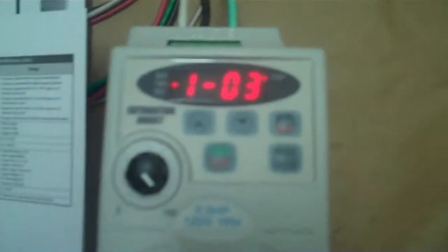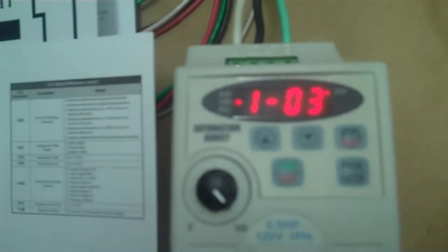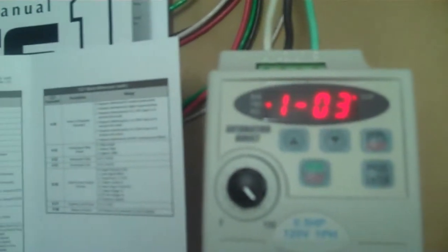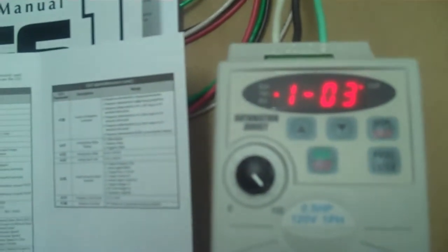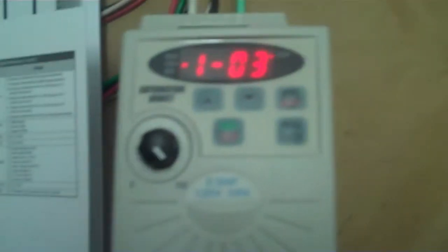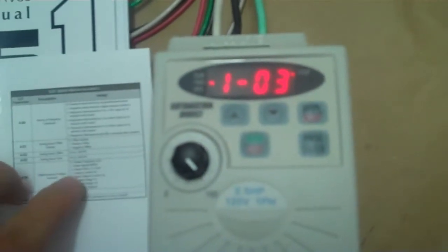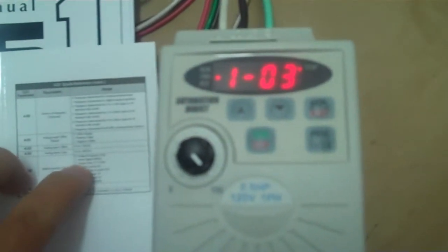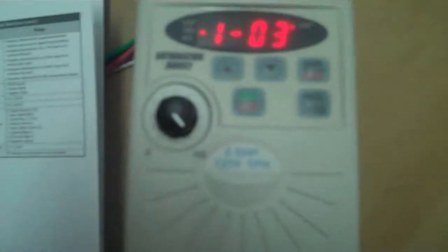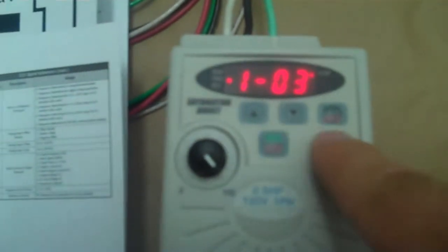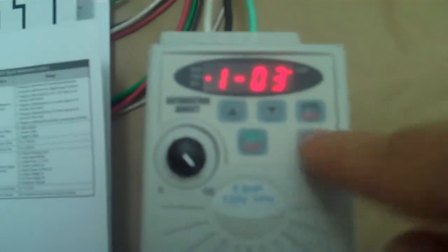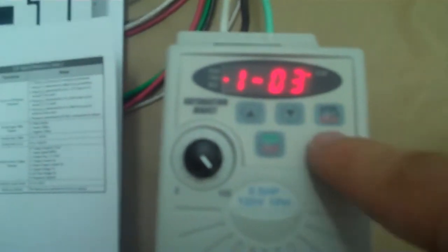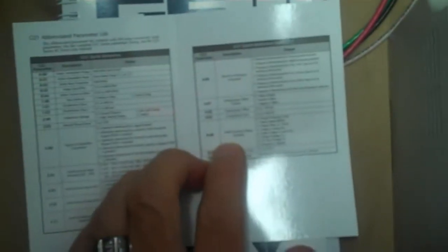Now the last piece that we're going to do is we want the controller to read by default, we want it to read motor RPM rather than frequency. RPM means something to me. Frequency I just don't really think about frequency all that much and I don't know who does. So let's get over to here right here, it's eight dash zero zero, multi-function output terminal.